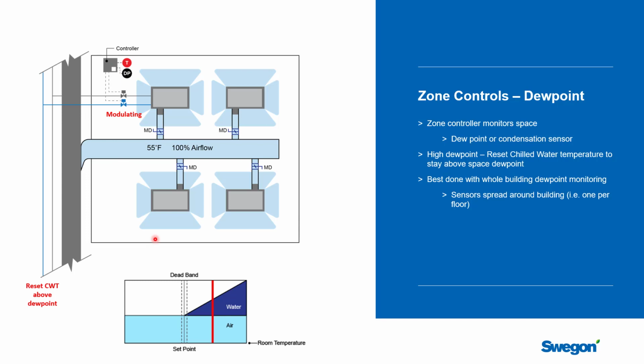So a different way to look at this is to say, we're going to monitor the dew point in the space. And if we start to get close to that dew point, we're going to start to raise the chilled water loop temperature. Normally they're designed for around 57 degrees, but as you get closer and closer to dew point, you might reset that chilled water to 58 or 59. You will absolutely give up cooling capacity for all the chilled beams that are hooked to that water loop. That's the downside. The upside is we can keep modulating chilled water into all the zones to help manage the cooling effect until we can get the primary air to dry the space out.